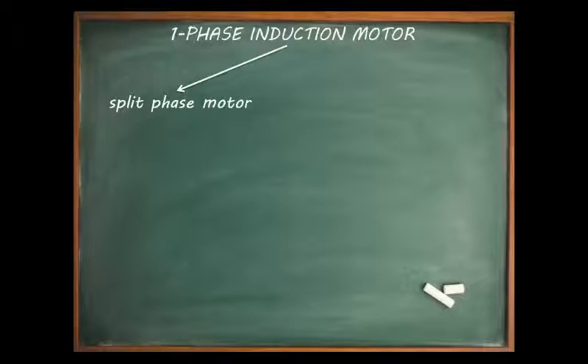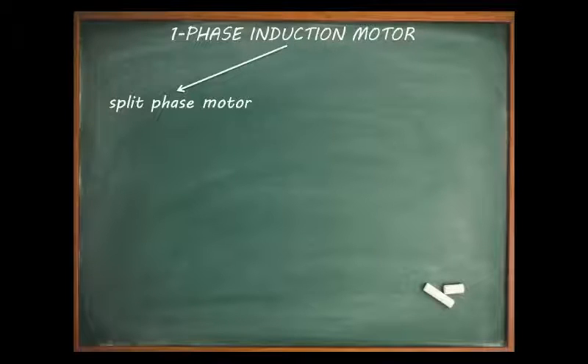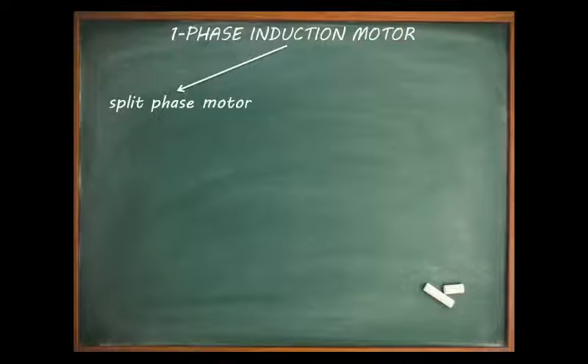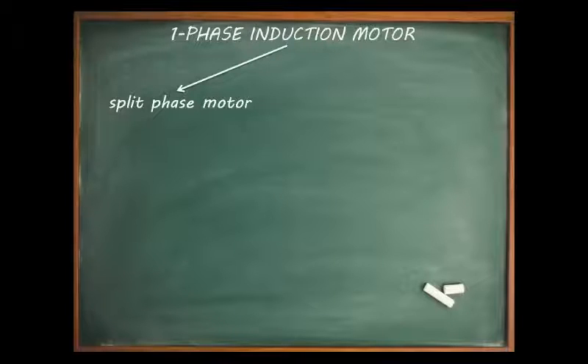If done properly, the current may differ by 90 degrees, thereby creating a rotating magnetic field from a single phase supply. This is the principle of the split phase induction motor, and single phase motors classified according to this principle are as follows.